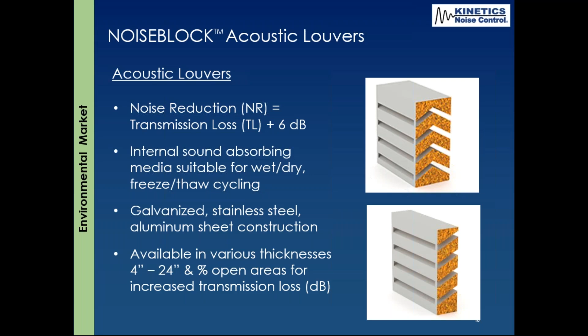What you're looking at on the right are the solid surfaces of the acoustic louvers. Underneath each air passage is a perforated sheet, and as noise propagates through the air passages, some of that sound energy penetrates the perforations and gets absorbed into the media fill. They're available in many different constructions and materials, in thicknesses from 4 to 24 inches, with various percent open areas. The importance here is that we have enough product options that, depending on the application, we don't want to affect the performance of that air-cooled chiller. We can tune the products we offer to get the right minimal, extreme minimal back pressure, but still get the acoustics we need.